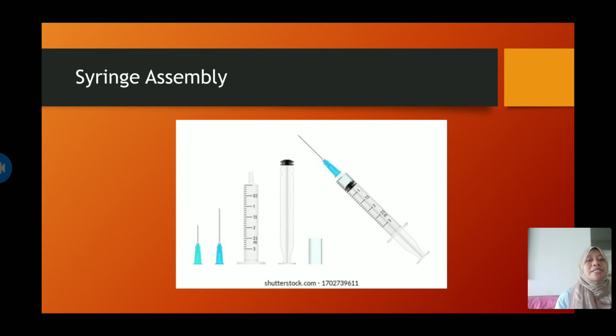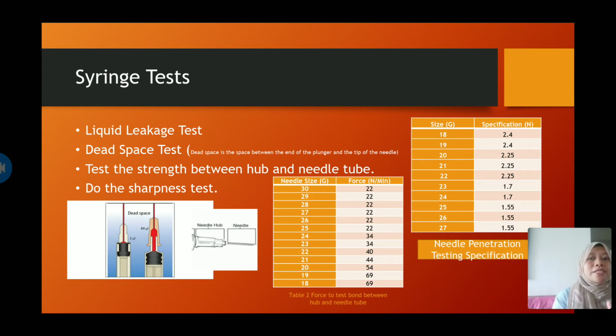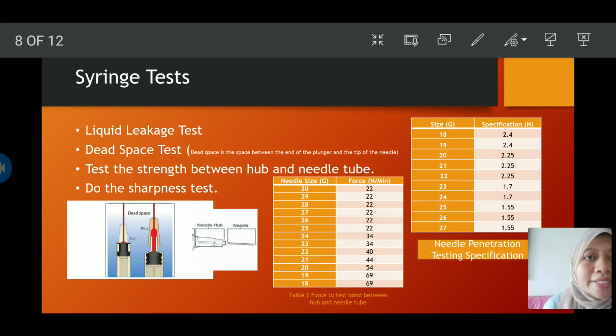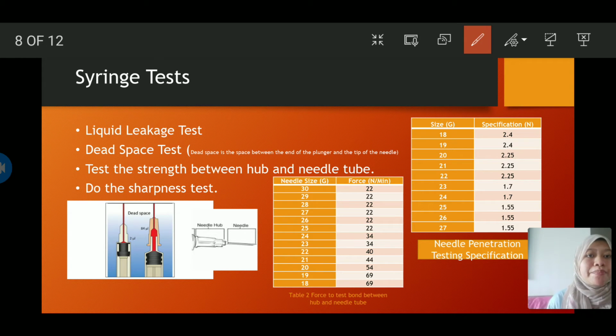where the barrel, the plunger, the gasket and the needle are assembled via the machine. In this stage, I do about 4 tests. The first is the liquid leakage test, the same thing that I did earlier. The second is the dead space test. The dead space is the space between the end of the plunger and the tip of the needle. If you look at this picture, we want to know the value of the red area, so that for things such as blood or vaccine, we can measure how much is left in the syringe.